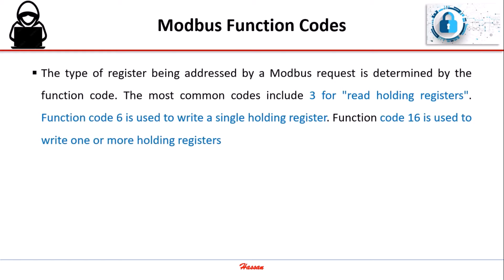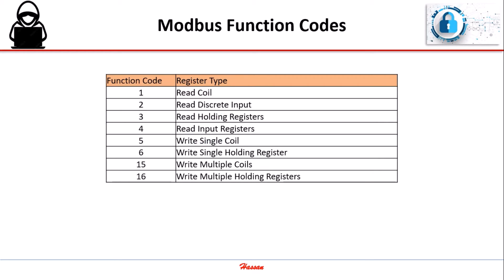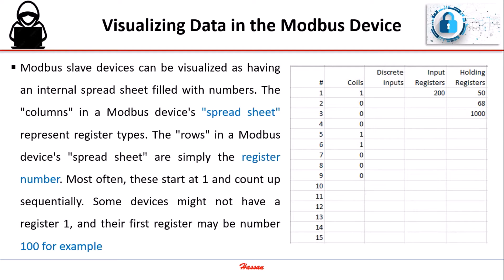The type of register being addressed by a Modbus request is determined by the function code. The most common codes include function code 3 for read holding registers. Function code 6 is used to write a single holding register. Function code 16 is used to write one or more holding registers. Modbus slave devices can be visualized as having an internal spreadsheet filled with numbers. The columns represent register types, and the rows are simply the register number, most often starting at 1 and counting up sequentially. Some devices might not have a register 1, and their first register may be number 100, for example.